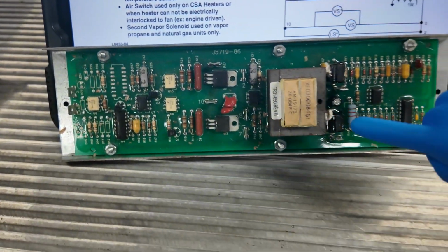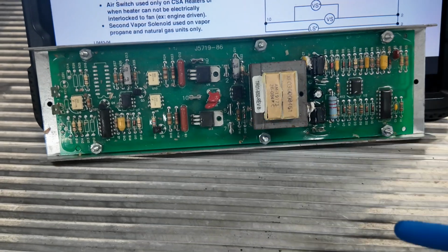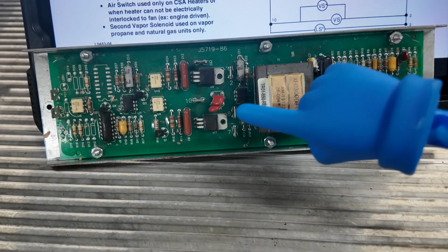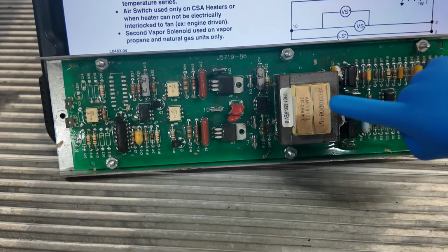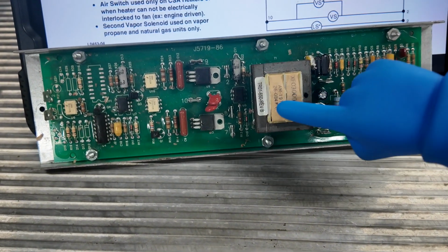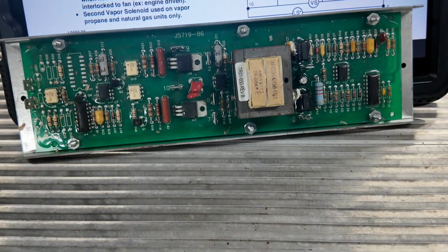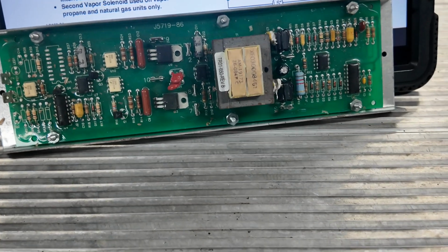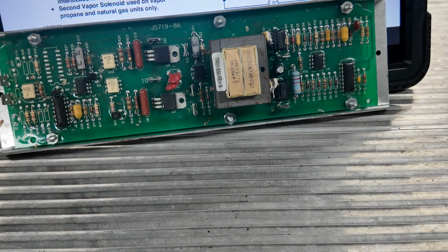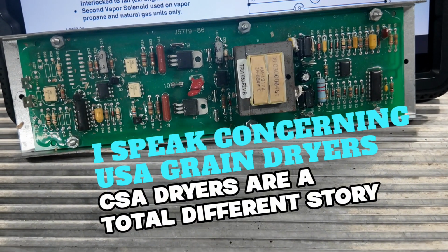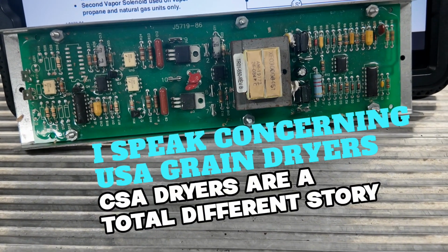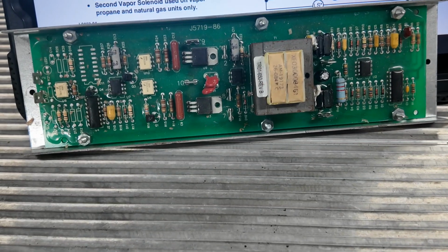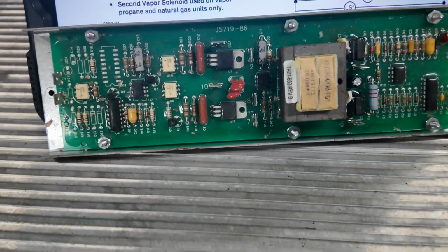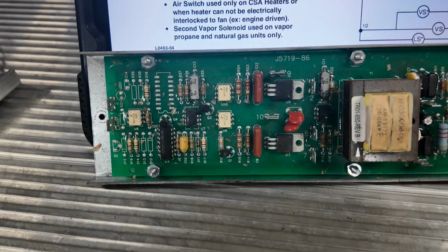And this is the way it's normally mounted in the side of the box, either this way or sometimes vertical. But we're going to start this way because this is how fan heaters have them. But this same board is used in fan heaters, portable dryers, mixed flow dryers. All of their grain dryers use this style burner control, except for tower dryers. Tower dryers are the only thing that use a different burner control. They use a Siemens.